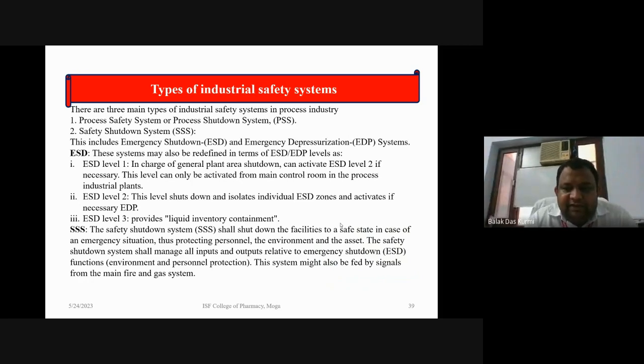The safety shutdown system shuts down the facilities to a safe state in case of an emergency situation, thus protecting personnel, the environment, and the assets. The safety shutdown system shall manage all inputs and outputs related to emergency shutdown function, environment, and personnel protection. This system might also be fed by signals from the main fire and gas system.